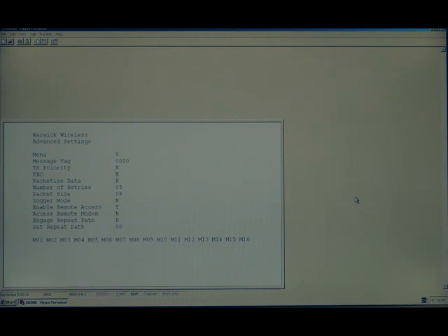There's a forward error correction which will put in redundant bits, and the distant modem will reconstitute the data. All radio modems in the network have to have forward error correction set if it's used. Data can be packetized, the number of retries set, and the packet size. This is only used in back-to-back radio modem systems, not networks.